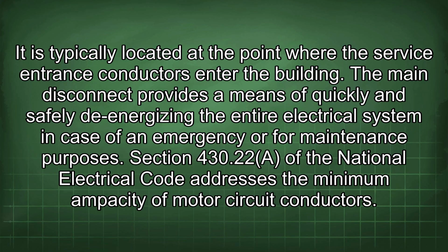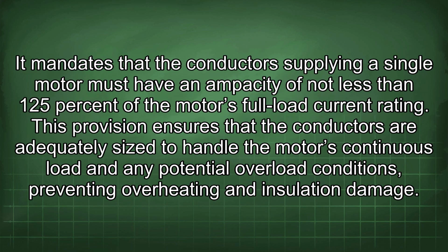Section 430.22 of the National Electrical Code addresses the minimum ampacity of motor circuit conductors. It mandates that the conductors supplying a single motor must have an ampacity of not less than 125% of the motor's full load current rating. This provision ensures that the conductors are adequately sized to handle the motor's continuous load and any potential overload conditions, preventing overheating and insulation damage.